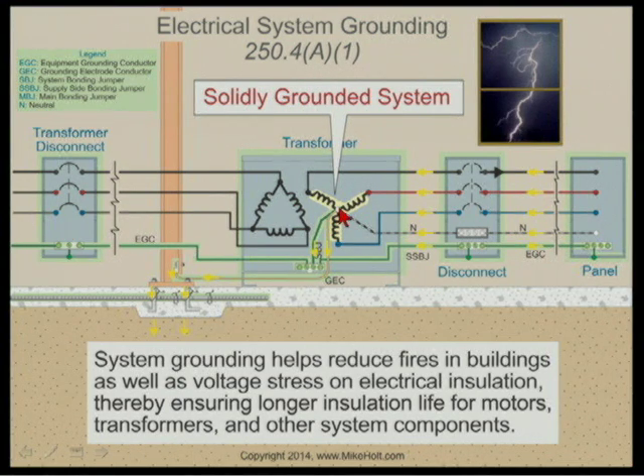And then we're taking this system, and more importantly here, we are grounding it to some conductive body that extends the ground connection. By having a system that is grounded like this, back in Beeman's book talking about all these overvoltage conditions that could take place, this ground connection from the case, from the system itself, allows a method for that charge, for restriking ground faults or ferroresonance or induced charges from lightning, whatever it might be, that energy can be displaced because it's trying to get to the earth. And that's why we've chosen to go with grounded systems.